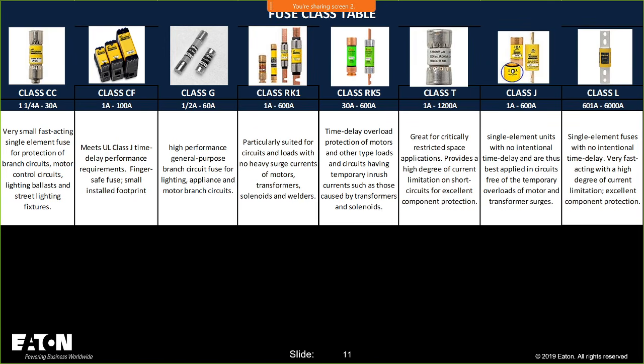The Class CF, again, small installed footprint. That was basically Class J fuse performance put into a different footprint, so that we can make a panel board that has a much smaller footprint, smallest in the industry, and could be used as a panel board in, say, Article 700 systems, et cetera, or data centers, things like that. And also industrial control panels use Class CF fuses. They're a nice finger-safe solution. And then you have your Class Gs. It's a branch circuit fuse for lighting, appliances, and motor branch circuits. Only goes up to 60 amps.